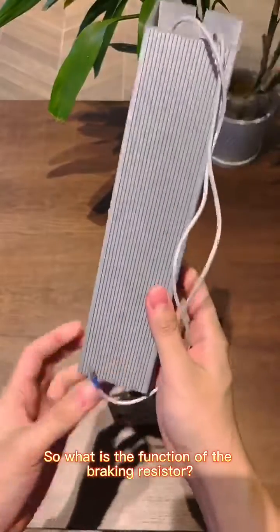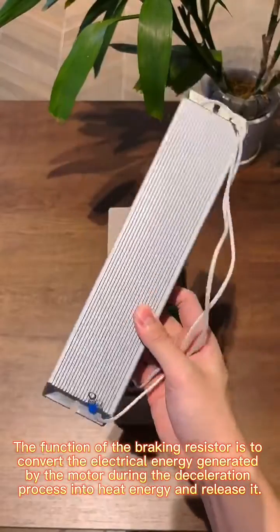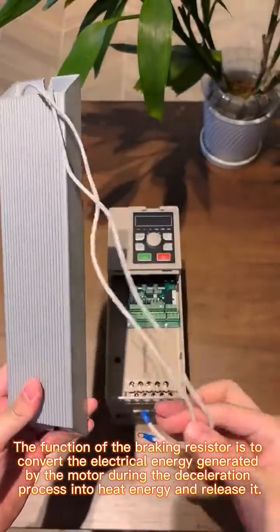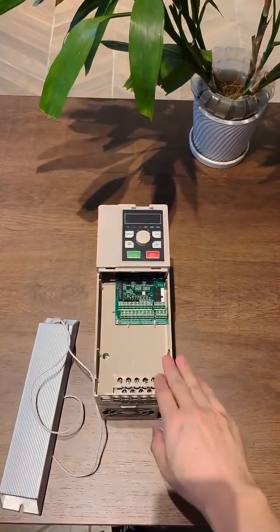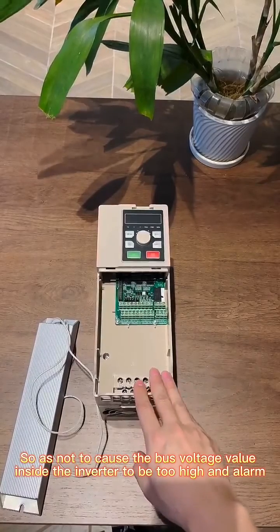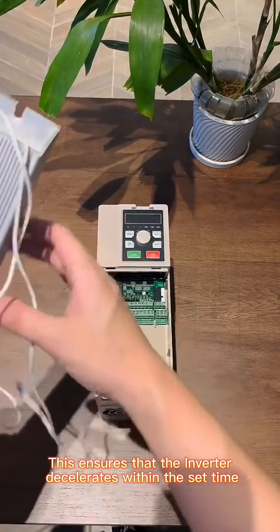So what is the function of the braking resistor? The function of the braking resistor is to convert the electrical energy generated by the motor during the deceleration process into heat energy and release it, so as not to cause the bus voltage value inside the inverter to be too high and trigger an alarm. This ensures that the inverter decelerates within the set time.